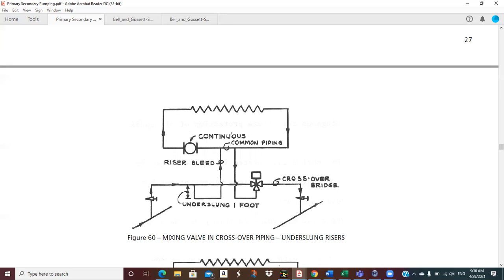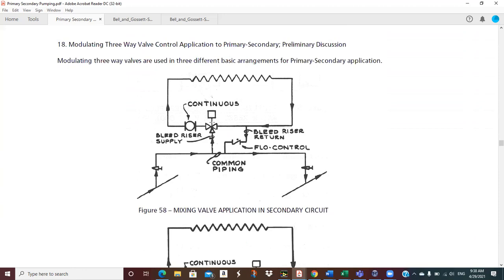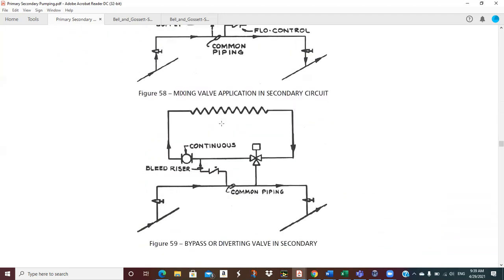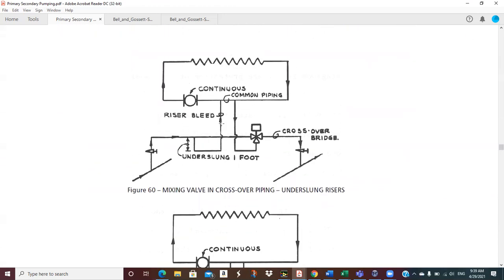But if you're in a heating application, our old example is we have 10 GPM up here and 40 GPM up here. So if I put that control valve in the secondary, like we show up here, then I'm trying to control 10 GPM with a control valve that's sized to handle 40 GPM, and my controllability sucks, you know? So let's get smart and realize that in a heating situation, this is the flow I have to control. So let's put the valve down here where it can be sized, in his pipe sizing example, at 1 1/4. And so we get a 1 1/4 inch valve, which is cheaper, and will control this flow much better than a 2-inch valve sitting up here that's sized for 40 GPM. So that's the first advantage of this arrangement over those previous ones.